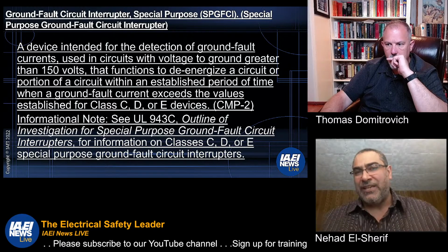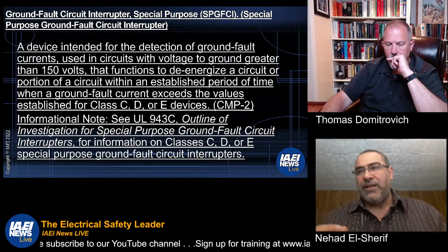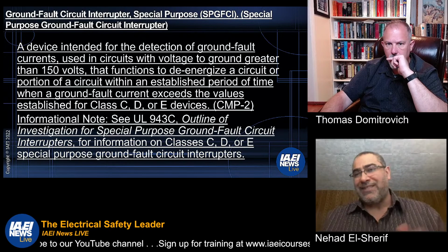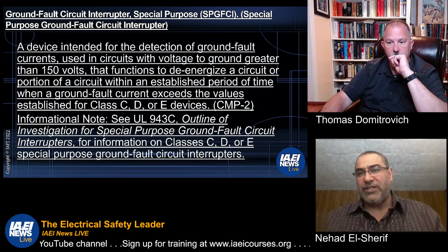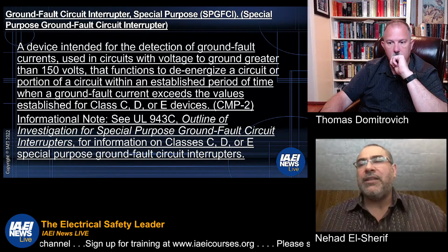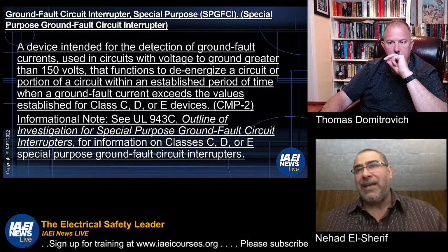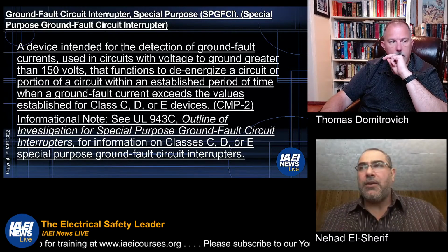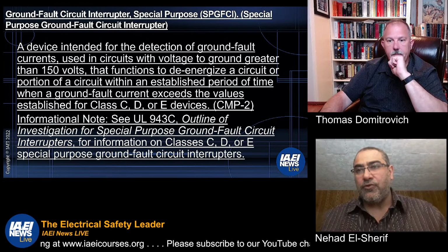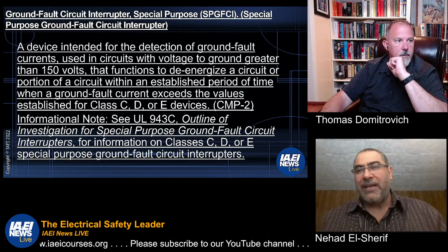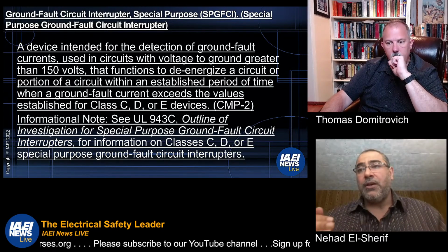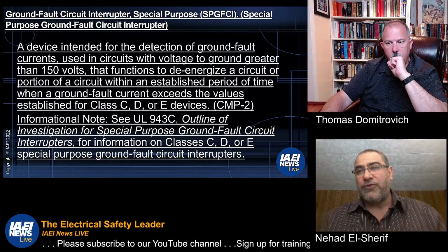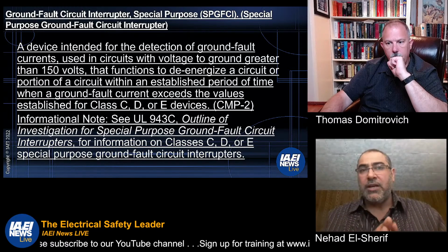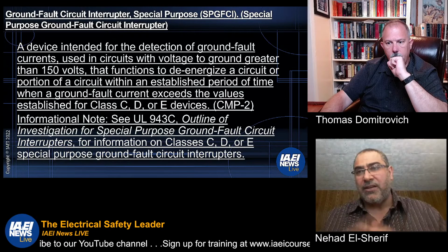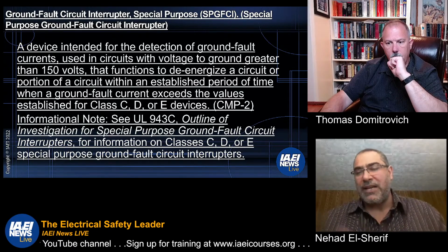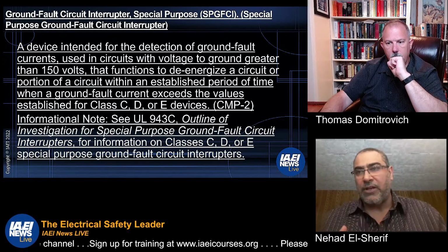An outline investigation, again, it's not that it's inferior to a standard. The difference between a standard and an outline of investigation from a UL perspective is that the outline of investigation is a document that has not gone through the ANSI process to qualify as a standard, but the requirement is still valid and it can be used for certifying products, and it's just as safe as a standard. It's just a matter of paperwork, and my understanding is UL has a long list of outline investigations.